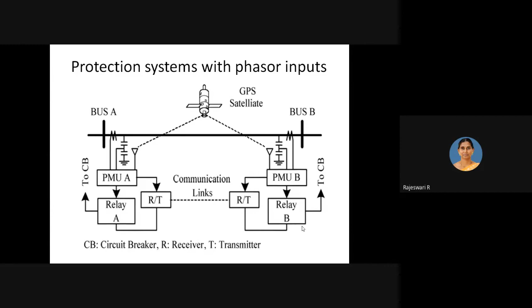So when you apply the PMU, that is, if you connect the PMU at the two ends of the line to be protected, at the two ends here, bus A and bus B, then with the available synchronized measurement of the data, if the differential scheme is operating, it would give a correct operation. The easy availability of synchronized measurement using GPS technology and the improvement in communication technology make true differential protection possible, improving line protection performance using phasor measurement at the remote ends of the line.